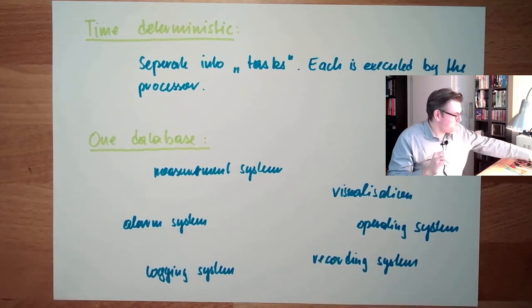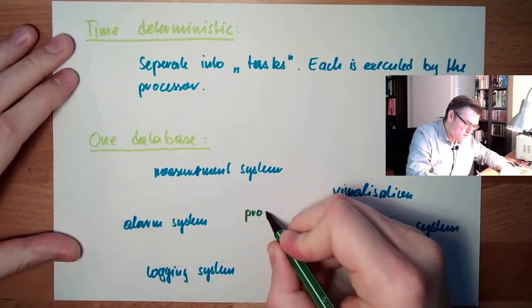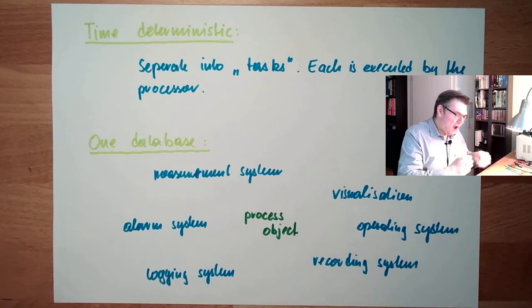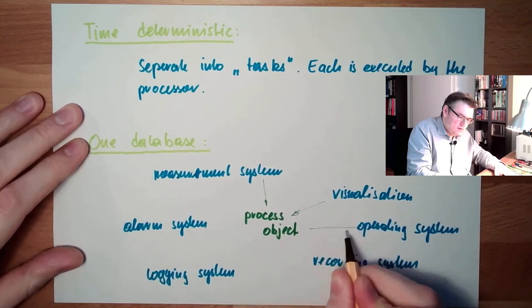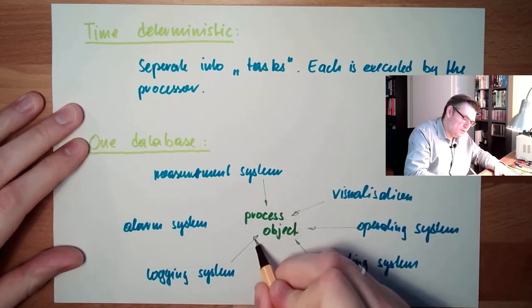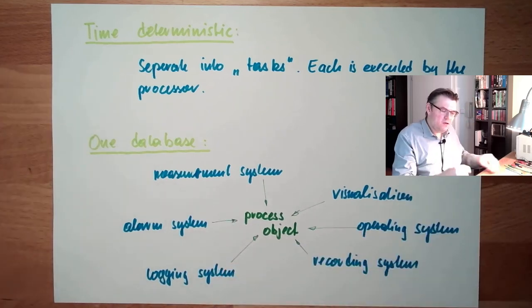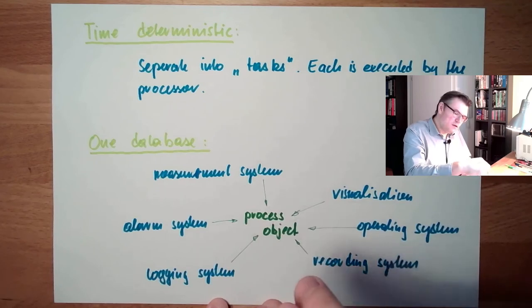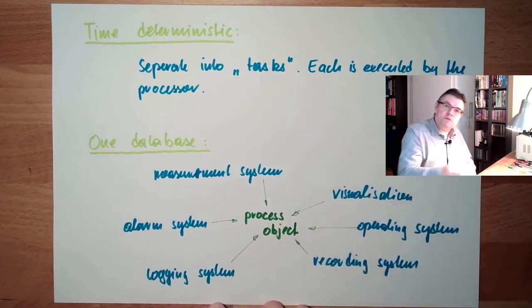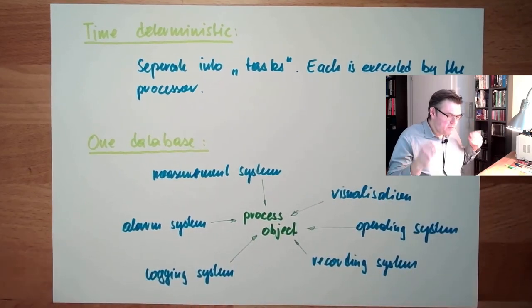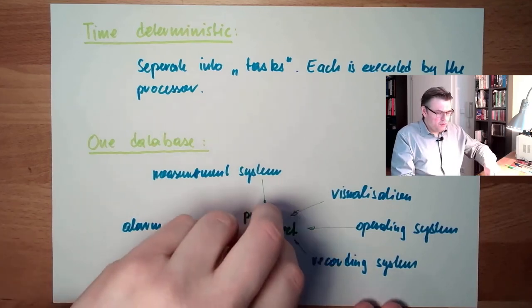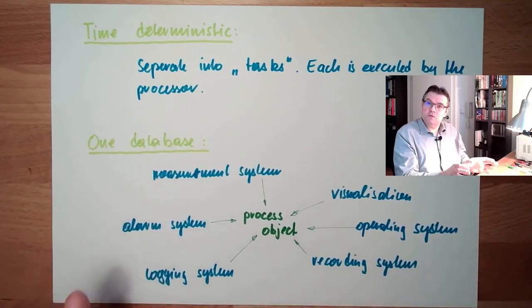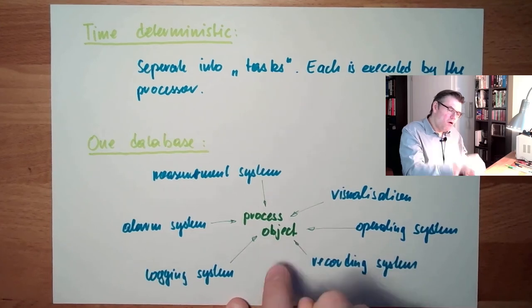There is one central process object, and all the other systems — measurement, alarm, recording, logging — are accessing this same process object. If I want to add a visualization and up to now I have none, I do not copy the process object. I simply add the visualization and say 'visualize this object' — it is already there. This is a typical design of a process control system: a model of the process with process objects, and all other parts refer to this one object in one database.